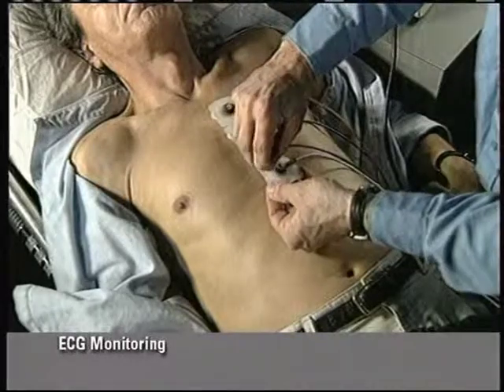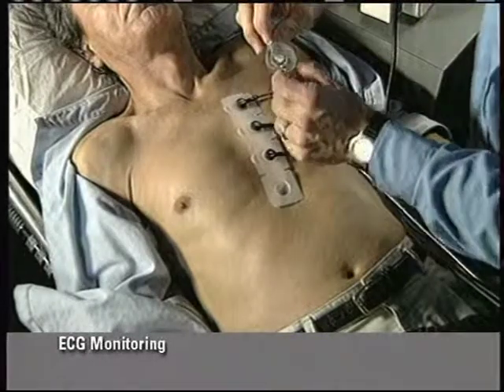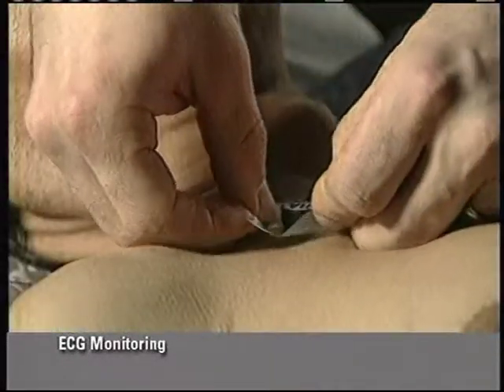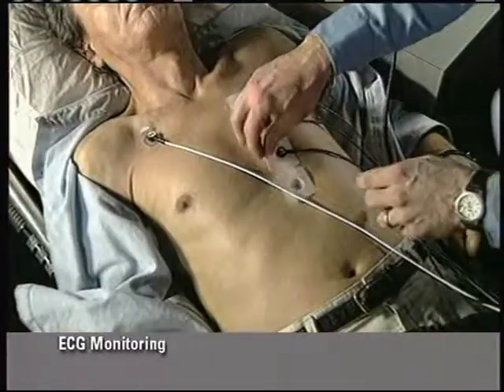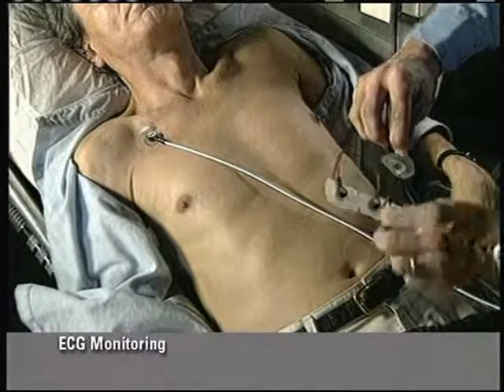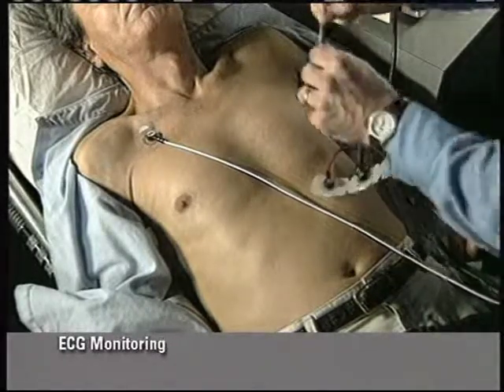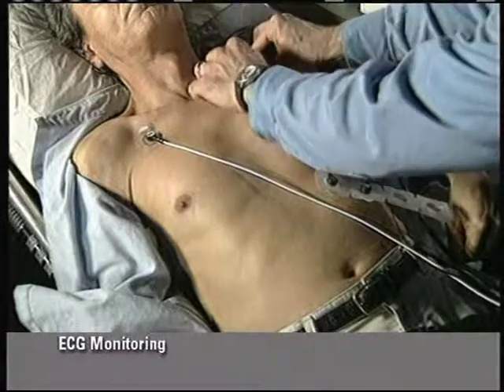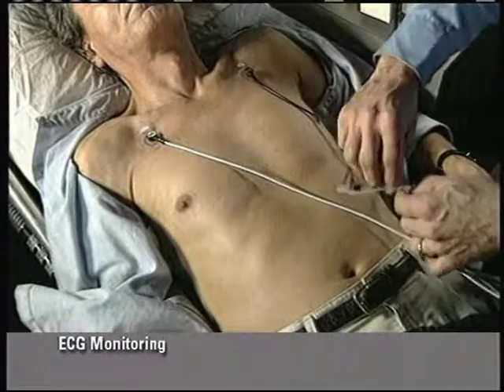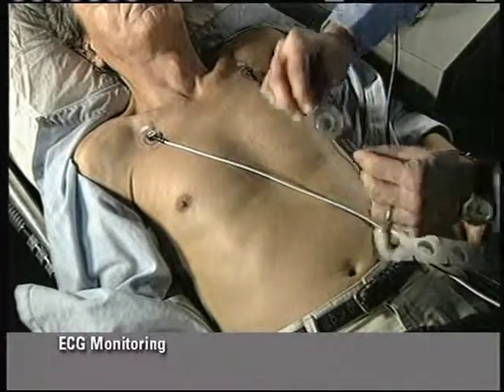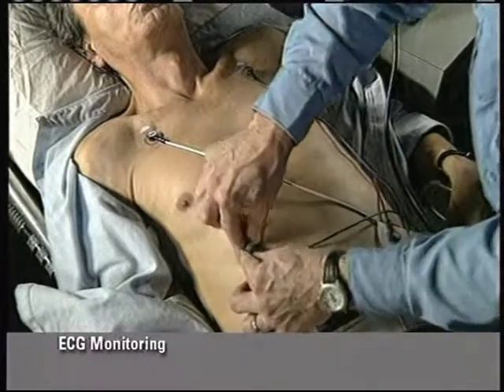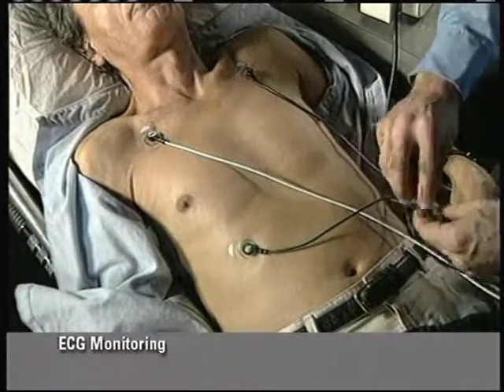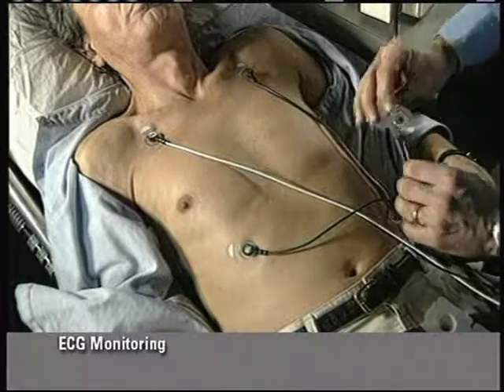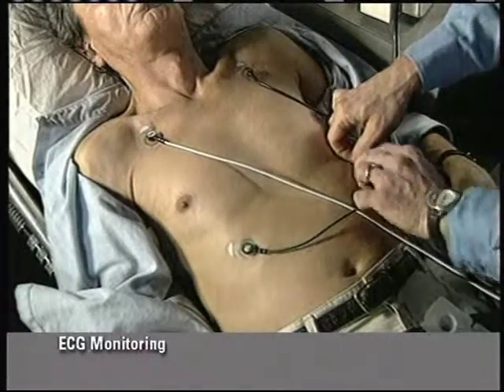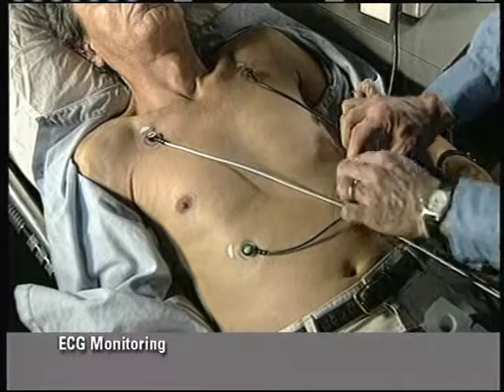Remove the electrode from the carrier and check that the gel is intact. Holding the electrode taut with both hands, apply the electrode flat to the skin. Avoid pressing the center of the electrode. Place the white right arm electrode on the patient's upper right chest below the clavicle. Place the black left arm electrode on the upper left chest below the clavicle. Place the green right leg electrode on the lower right chest, and place the red left leg electrode on the lower left chest.